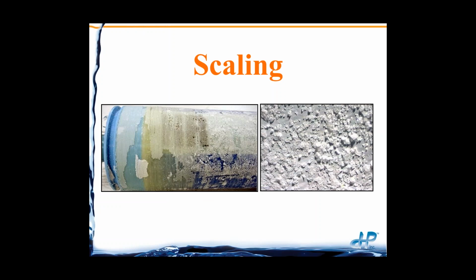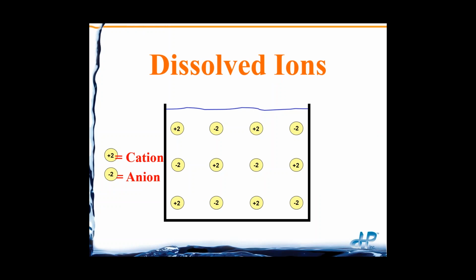Here's a picture of scaling on the outside of a membrane element on the left, and on the surface of the membrane when the feed spacer has been removed. So we see that we have crystals that are in the feed channel or the feed spacer as well.